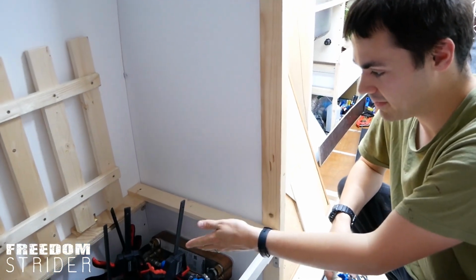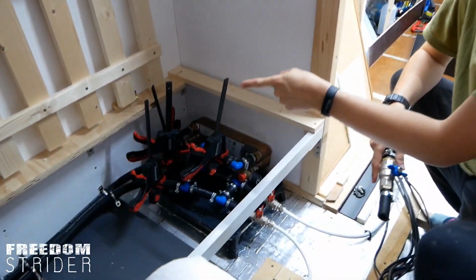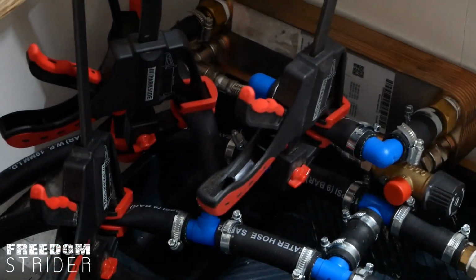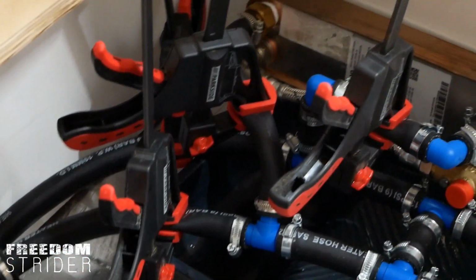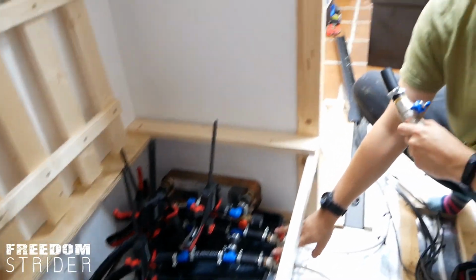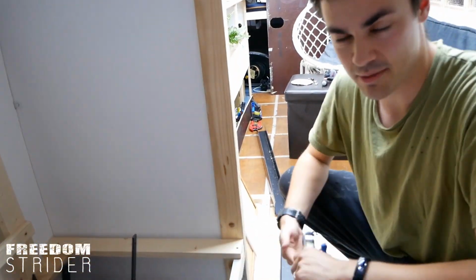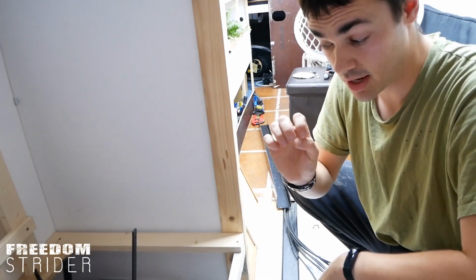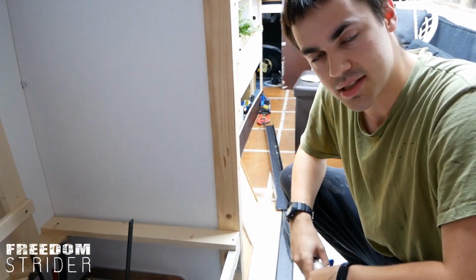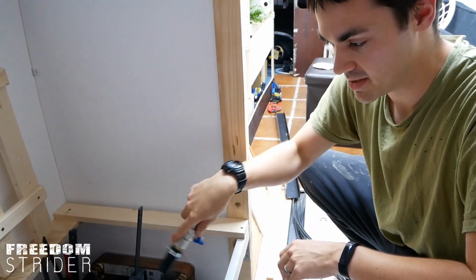So I've clamped off the entrance and exit to and from the heater, and also to and from the heat exchanger here, and I've shut the underfloor so that hopefully when we take that middle piece off, there should only be a small amount of glycol that leaks out of the remaining pipes in that piece.